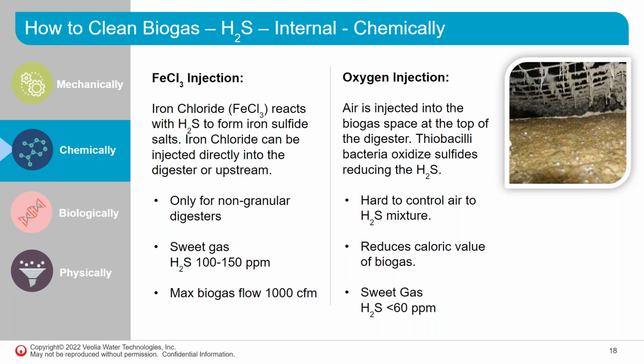And oxygen injection is actually a very good method, but it is kind of hard to control because you have to microaerate the headspace of the reactor, and you have to be very careful, because if you introduce too much air, then you create an explosive environment in the headspace of the reactor. But it is a very good method to remove hydrogen sulfide from the wastewater.